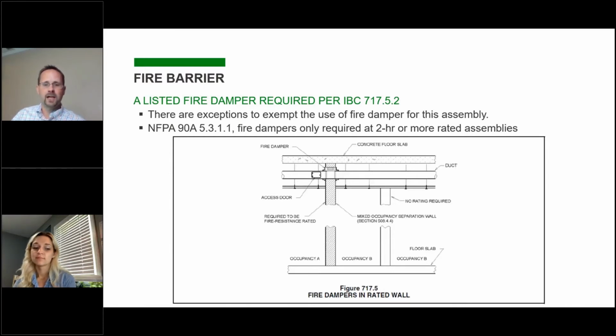And similar to the firewall, if it's a horizontal exit, it needs a smoke damper as well. So just looking at the plan and seeing a fire barrier, 1 hour, 2 hour, it needs to still have some discussion as to what the purpose of that fire barrier is, so you can have a complete understanding of how to handle it.